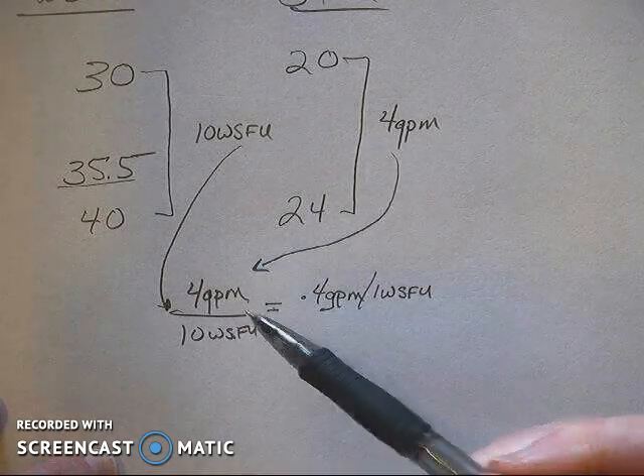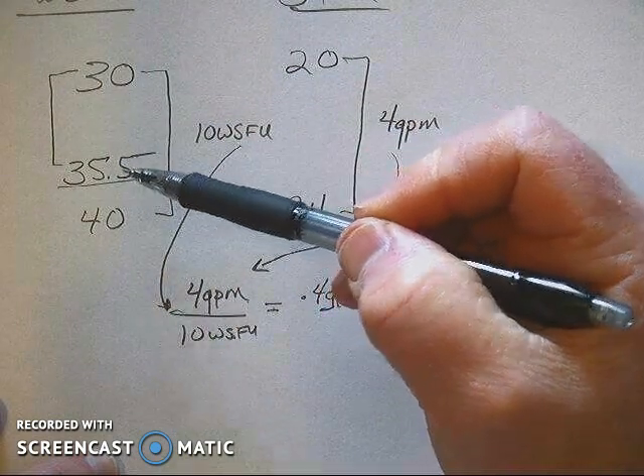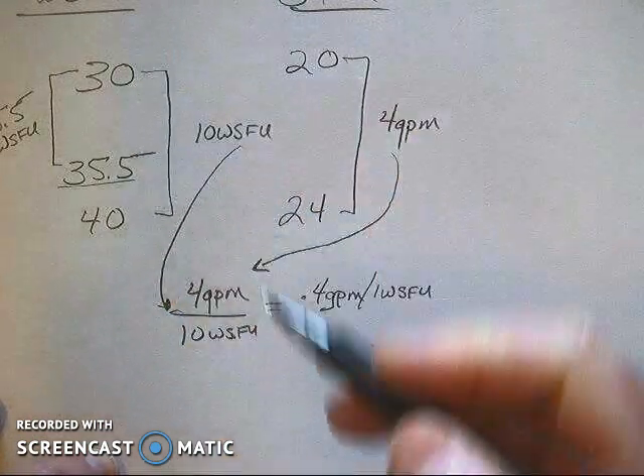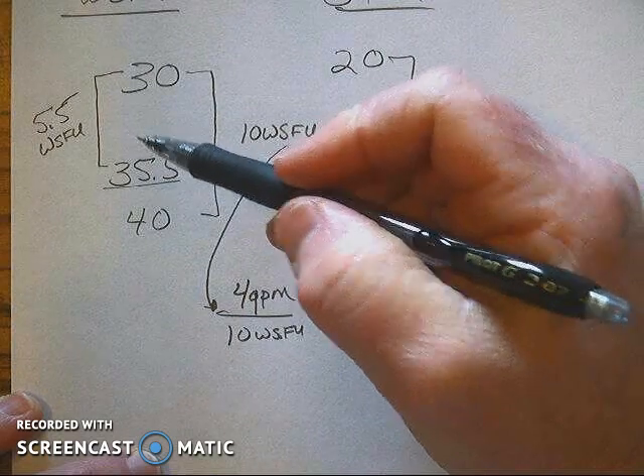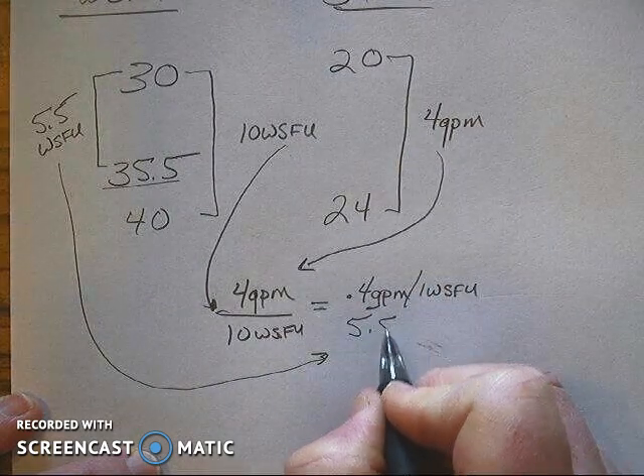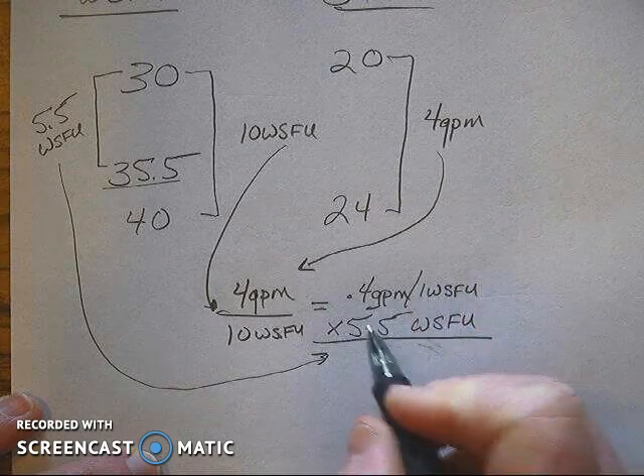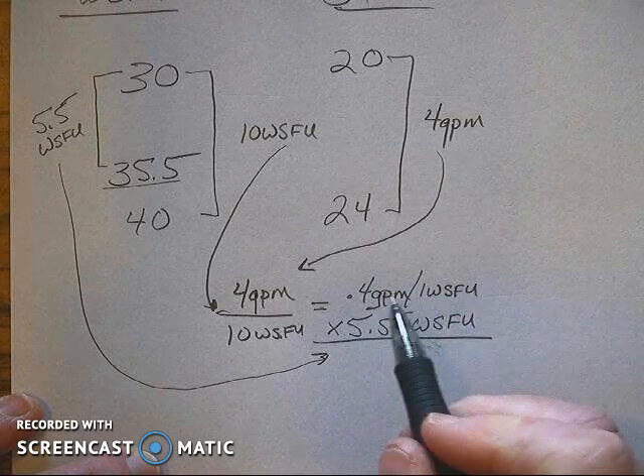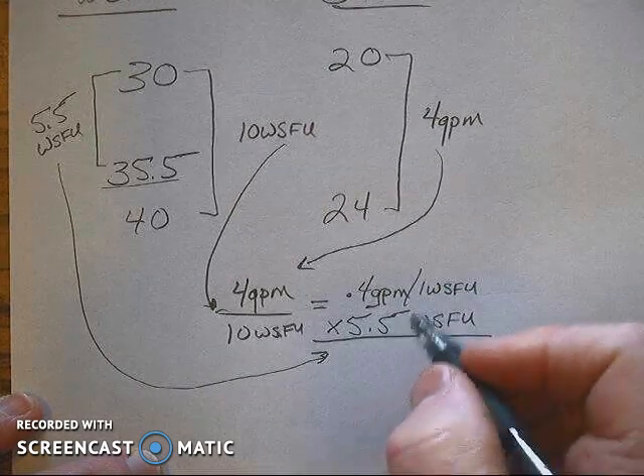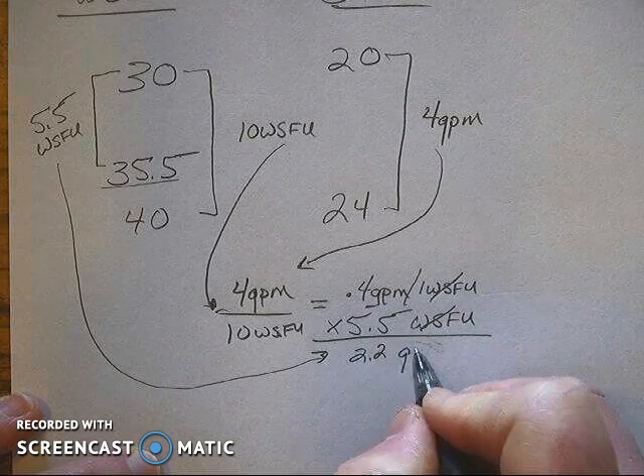Now when we look at our example we are looking for 35.5, and 35.5 WSFU is 5.5 WSFU more than 30 WSFU. With that said I'm going to take the 5.5 and bring it down over here and write that down, 5.5 WSFU. Now I'm going to multiply the 0.4 GPM per 1 WSFU times the 5.5 WSFU. When I multiply that out I'm going to get 2.2 and my WSFU is going to cancel out and my label will be in GPMs.